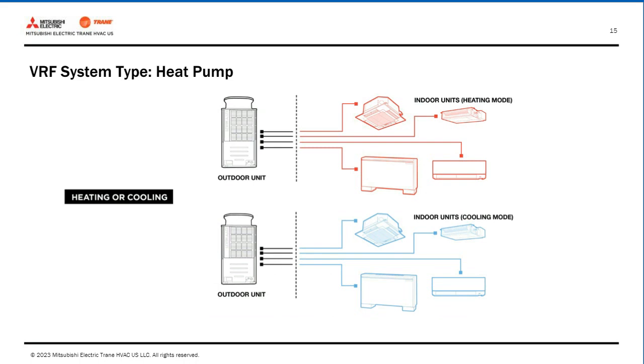So this is a slide showing one of our types of equipment, which is the heat pump. So in single zone applications and in moderate climates, the HVAC contractors will sometimes choose heat pumps. Heat pumps are an effective way when all the building zones can be in the same mode at the same time, so either heating or cooling. You can still have the individual set points on the indoor units, but the mode is the same. Either they're all in heating or they're all in cooling.